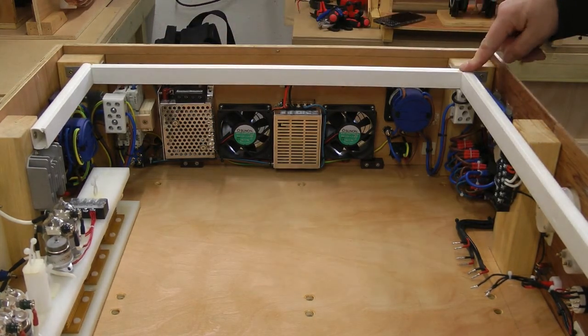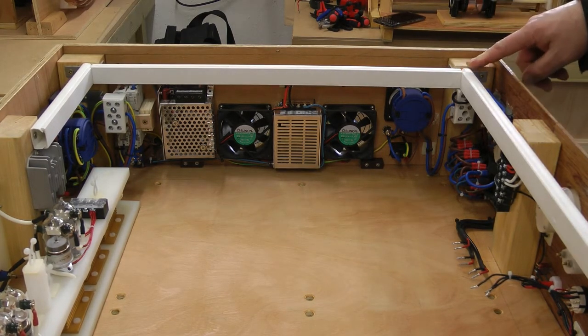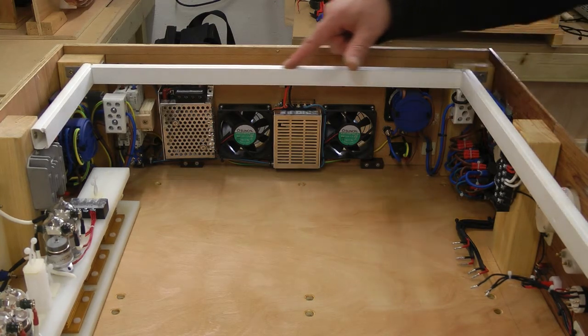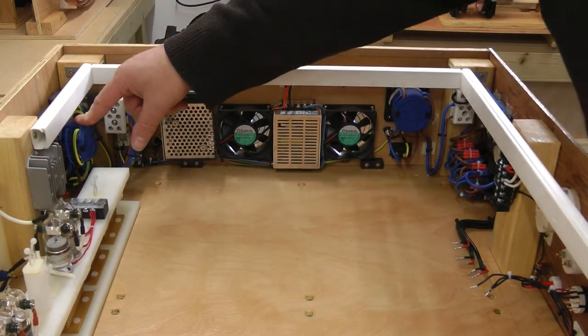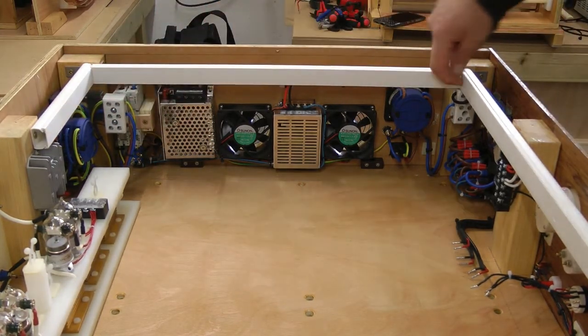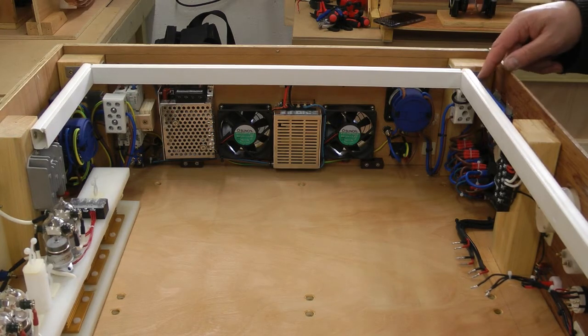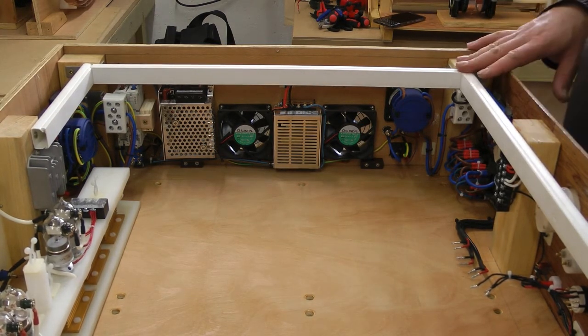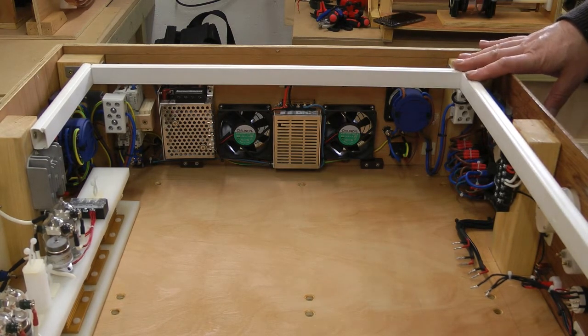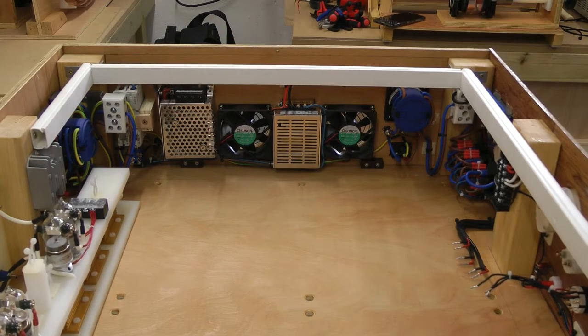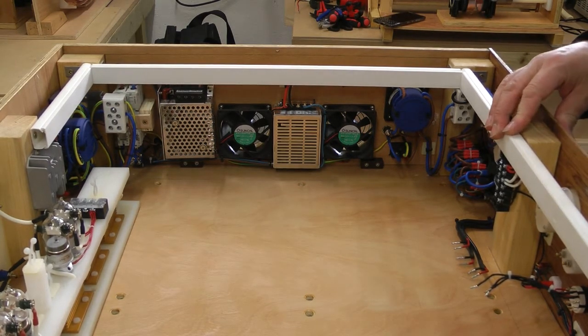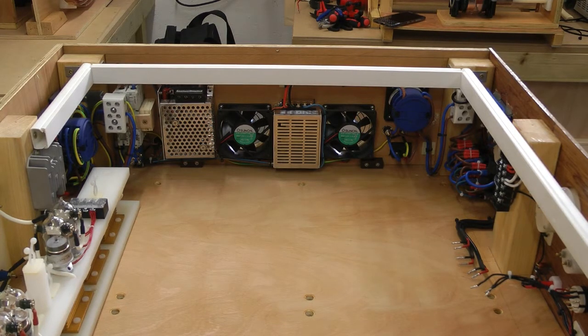Other wiring that goes in here, for example, if you switch to external power meter, you've got a return line going down here, out and into the external power meter switch, and obviously there's a line coming back which is feeding the neutral into the front panel. Otherwise, I think everything's relatively straightforward. They're simple components, easily available. Probably the most exotic components here are the vacuum relays, but otherwise this plate supply is intended to be very flexible, easy to use, easy to repair, yet you can use it in many different ways.